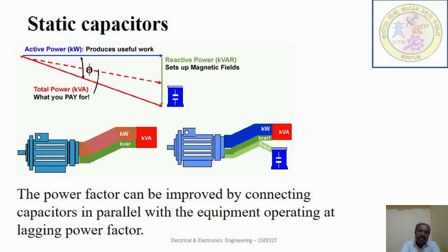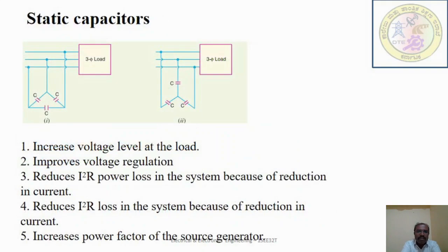If the motor is an induction motor, we know that it operates at low power factor. Locally, if you install the capacitor parallel to the induction motor, then the capacitor will inject the reactive power and it will reduce the reactive power, so that the power factor is improved. The power factor improvement is achieved by addition of a capacitor in parallel with the connected motor or light circuit, and can be applied at the equipment distribution board or at the origin of the installation.